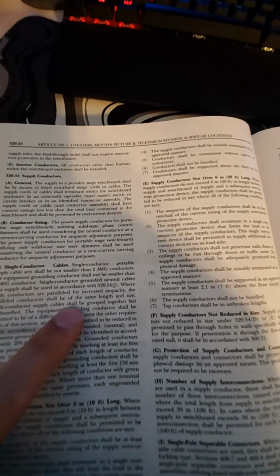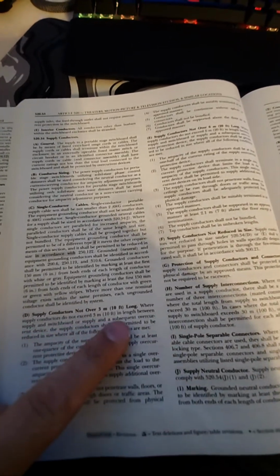Conductor sizing, it's probably going to be here. The power supply connectors for switchboards, sine wave dimmers, single conductors, number 6 here, grounded neutral cables, paralleled, neutral. I did not see it in there either. I don't see it in here. You can see where it's buried. This is actually a really good question. One that would take a lot of time.